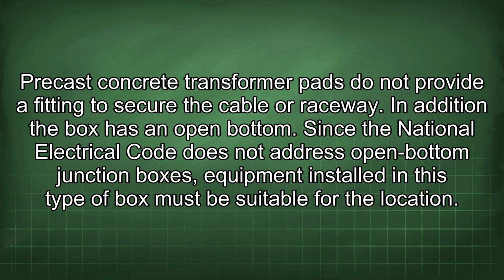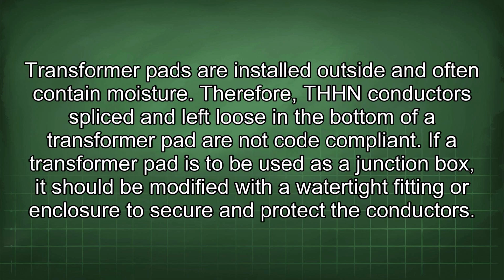Precast concrete transformer pads do not provide a fitting to secure the cable or raceway. In addition, the box has an open bottom. Since the National Electrical Code does not address open bottom junction boxes, equipment installed in this type of box must be suitable for the location. Transformer pads are installed outside and often contain moisture. Therefore, THHN conductors spliced and left loose in the bottom of a transformer pad are not code compliant.